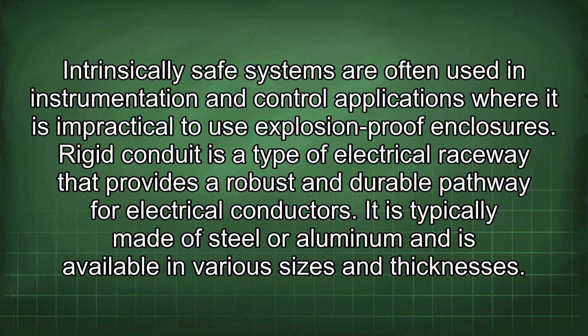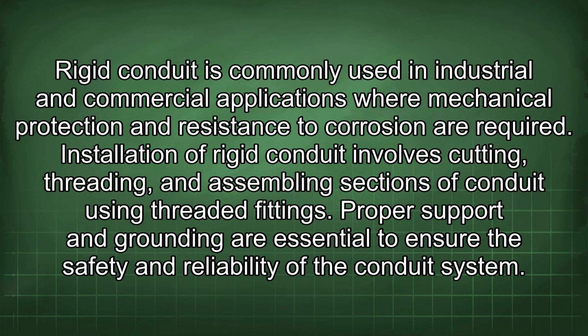enclosures. Rigid conduit is a type of electrical raceway that provides a robust and durable pathway for electrical conductors. It is typically made of steel or aluminum and is available in various sizes and thicknesses. Rigid conduit is commonly used in industrial and commercial applications where mechanical protection and resistance to corrosion are required.